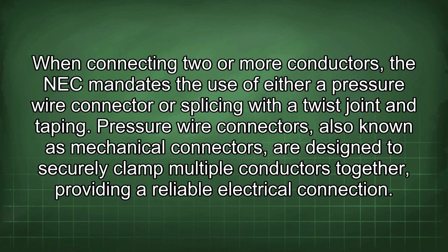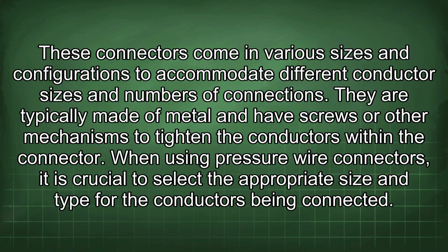When connecting two or more conductors, the NEC mandates the use of either a pressure wire connector or splicing with a twist joint and taping. Pressure wire connectors, also known as mechanical connectors, are designed to securely clamp multiple conductors together, providing a reliable electrical connection. These connectors come in various sizes and configurations to accommodate different conductor sizes and numbers of connections. They are typically made of metal and have screws or other mechanisms to tighten the conductors within the connector.